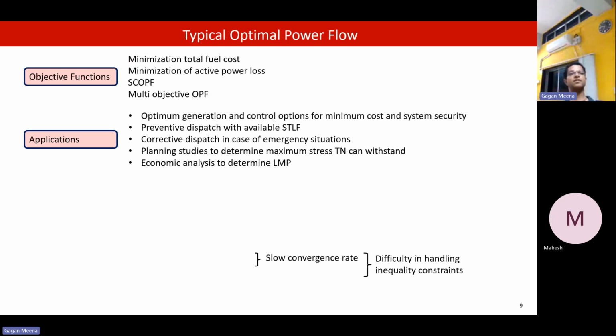These are the different objectives. Applications of optimal power flow: these two we have already discussed. One is preventive dispatch. With the available short-term load forecast, we can do a preventive dispatch. And in case of emergency situations such as line overload, or outages of even lines in case of some disasters, generally when cyclones are there and the wind velocity is quite high, in that case, some lines need to be, then corrective dispatch needs to be done.